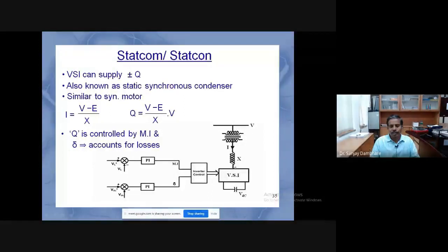The magnitude of this voltage can be controlled by the modulation index, and the phase angle can be controlled, with this voltage in phase with the line voltage. When current flows, based on the voltage difference between the two ends, that current will be quadrature in nature, and that quadrature current can help us in maintaining or controlling the reactive power.